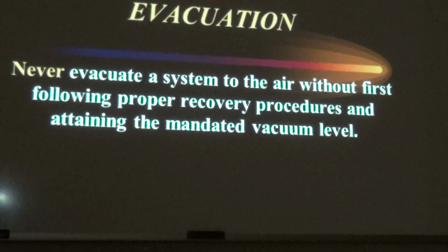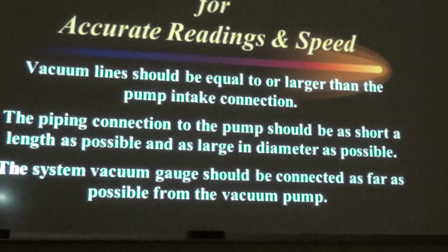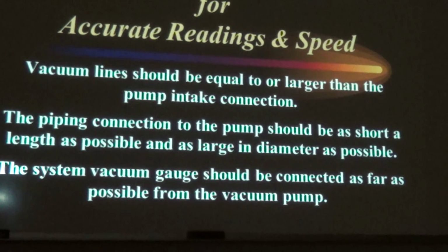Never evacuate a system to air without first following the proper recovery procedures and attaining the mandated vacuum levels. Here refers to that recovery efficiency chart that you're going to see. So, evacuation essentials, in other words, vacuuming essentials for accurate reading and speeds. What should they be? The vacuum line should be equal to or larger than the pump intake connections. That's your 5/8, your 1/4 inch connections. The piping connections to the pump should be as short as possible and as large in diameter as possible. The system vacuum gauge should be connected as far away as possible from the vacuum pump.